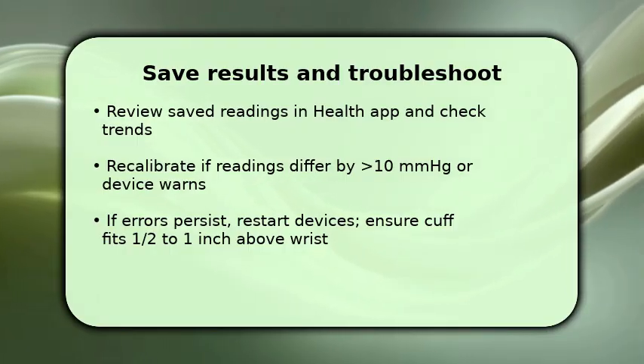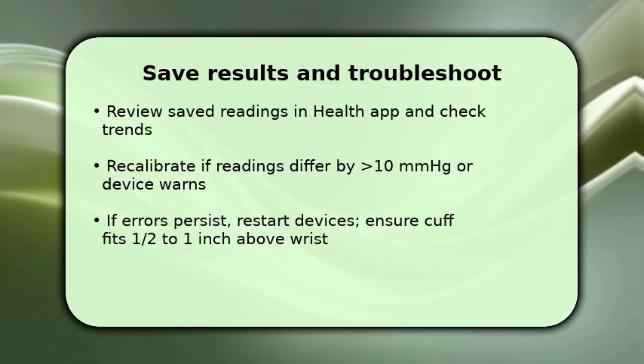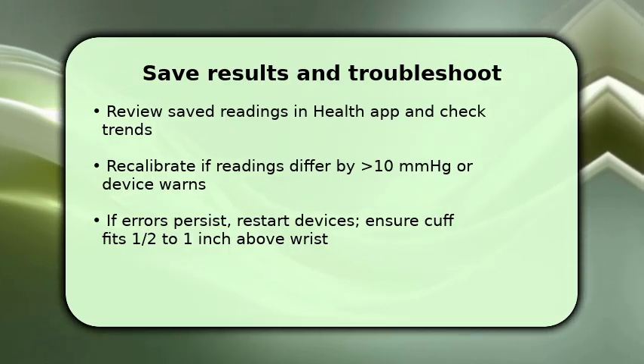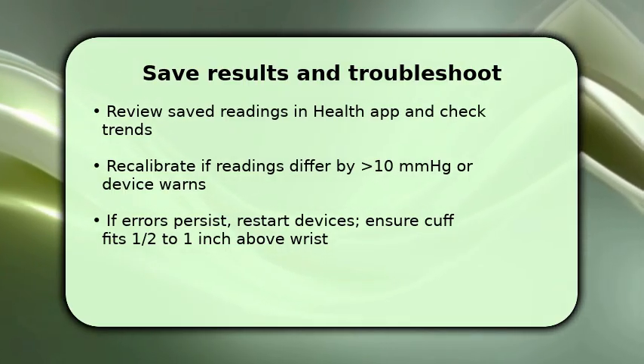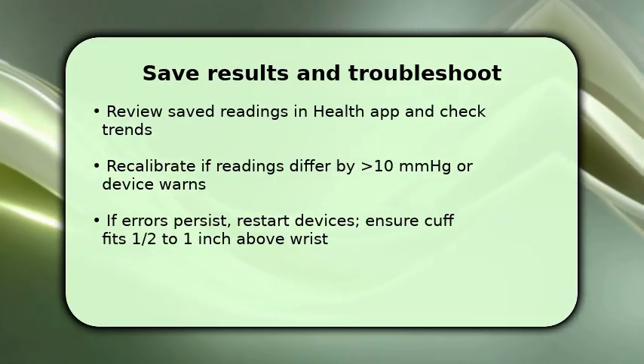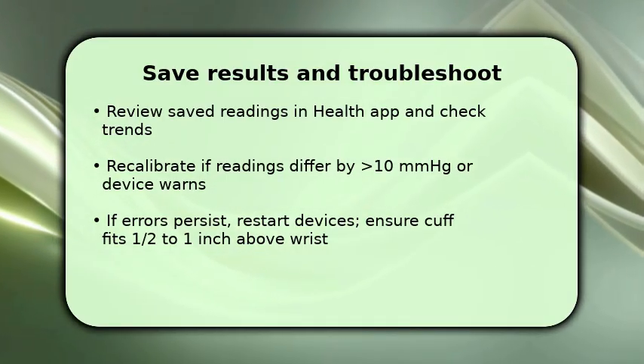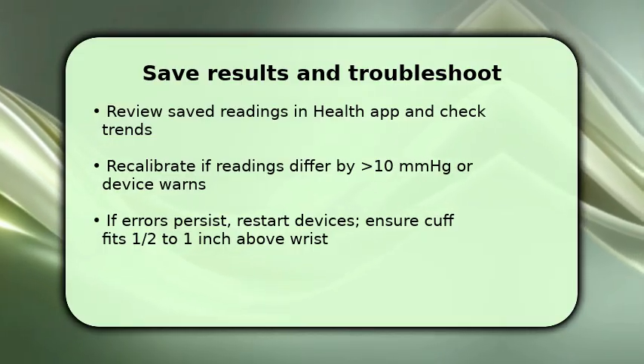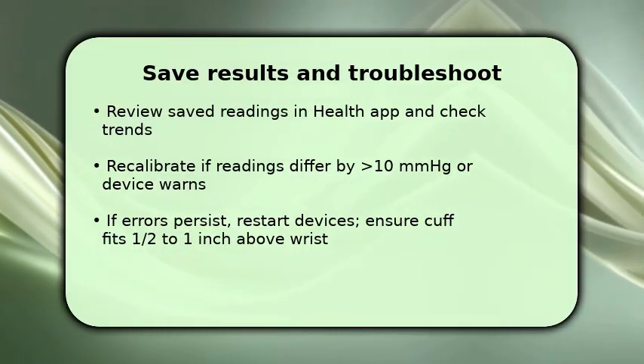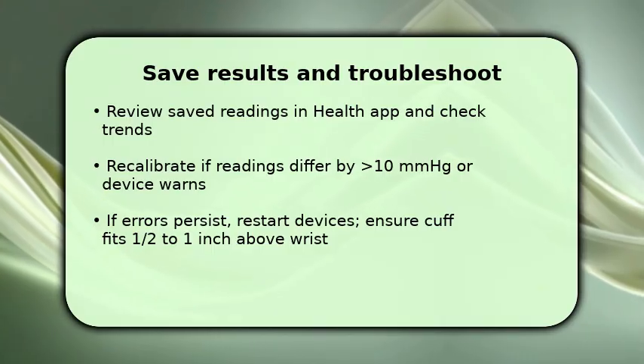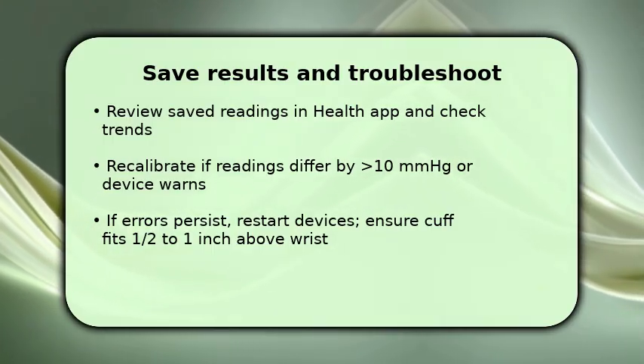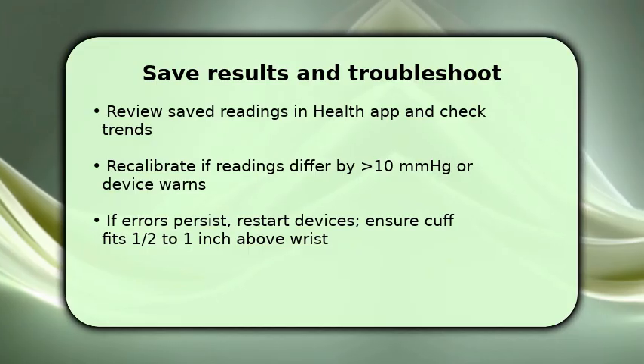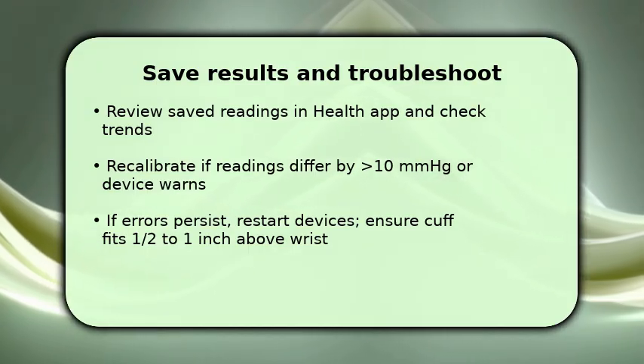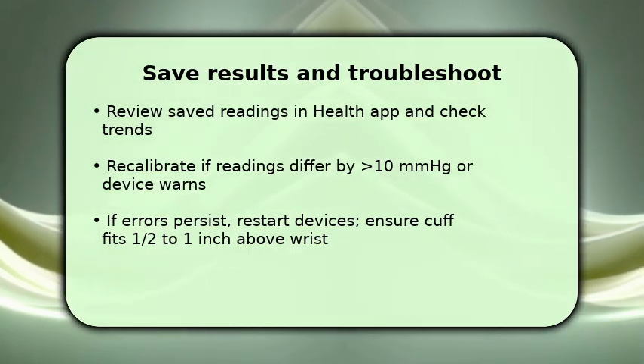After the result appears, confirm it's synced to the Health app and inspect recent values for consistency. This helps detect anomalies. If values differ significantly from a clinical cuff, recalibrate using the external cuff. Make sure the cuff is positioned about 1/2 to 1 inch above the wrist and snug but not tight. If problems continue, restart both devices, check Bluetooth, and retry. This resolves most connection or software hiccups.